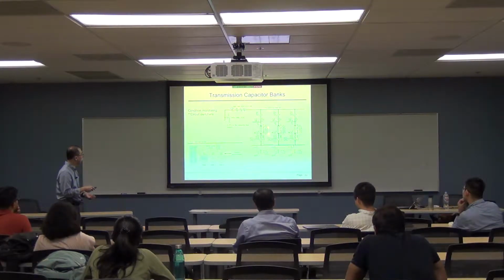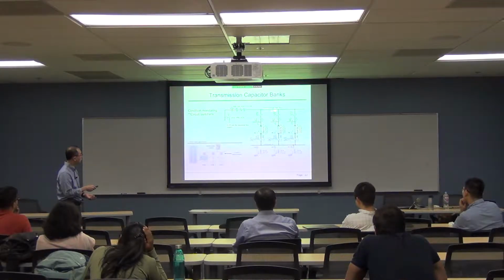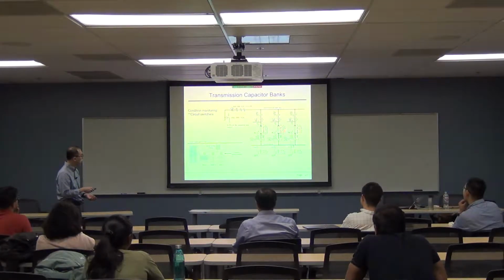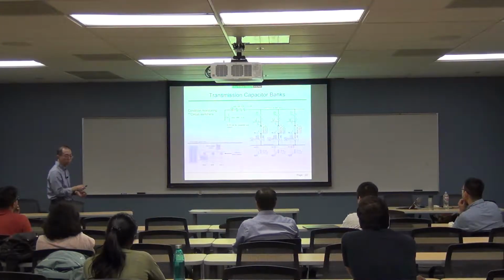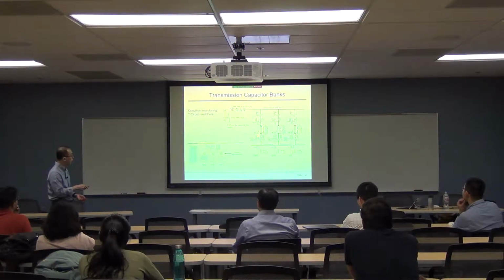In this particular application, you have a 161 kV capacitor bank bus, and this capacitor bus has three banks: bank number 1, bank number 2, bank number 3. The power quality monitor is measuring the voltage right here at the bus, and the current is measured right here. This is the circuit switcher right here, and this is a simplified view of that.